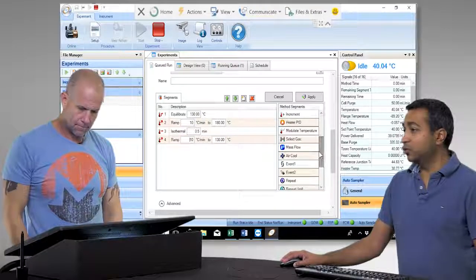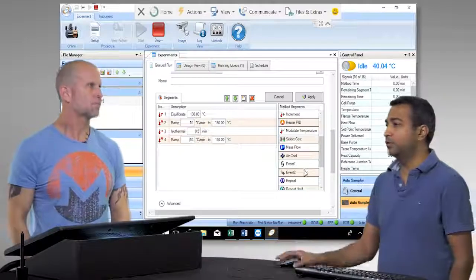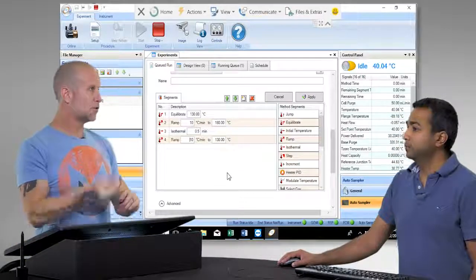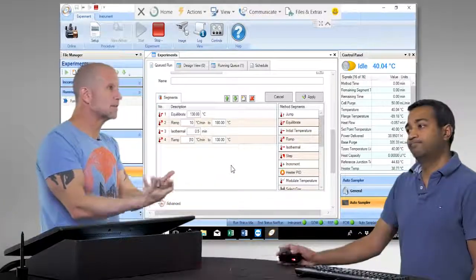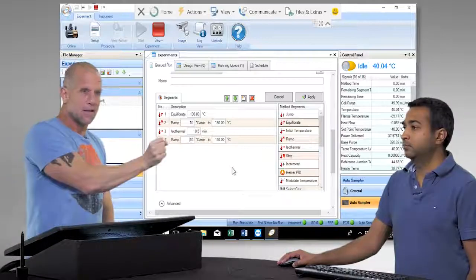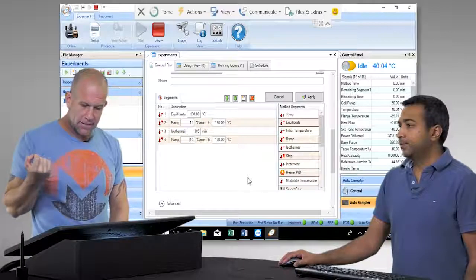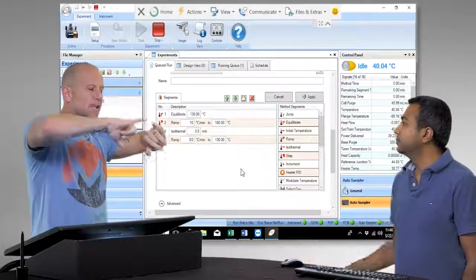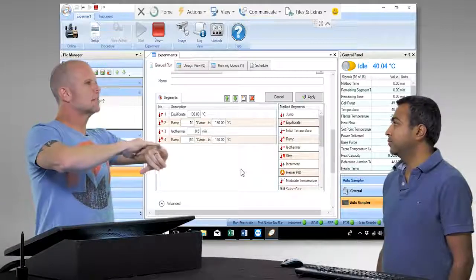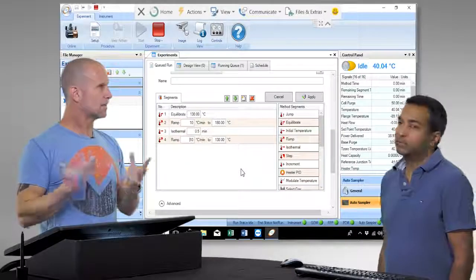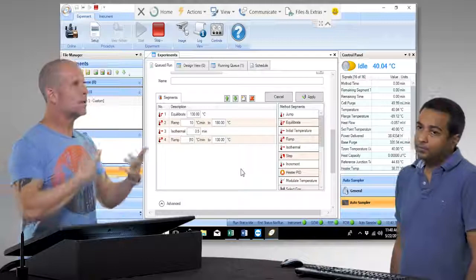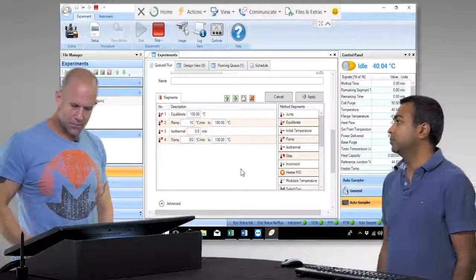It also gives you a lot of control over hardware — you can turn the chiller on and off, gas, all sorts of things. You can put one sample in the DSC and do a lot of different experiments, changing the hardware conditions and how you're ramping and holding conditions. The last thing to mention is that this is a modulated DSC. Instead of just linearly ramping, you can do a modulated frequency, which in a sense separates the thermodynamics and kinetics — which often can get confused — and gives a way to more accurately measure heat capacity.